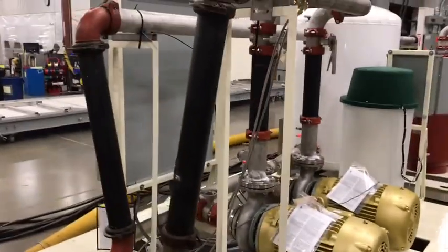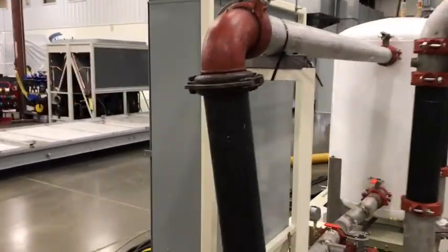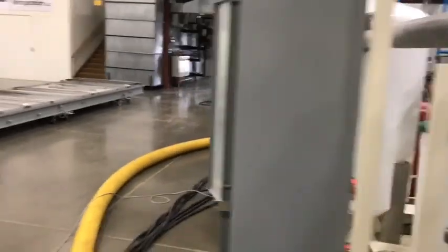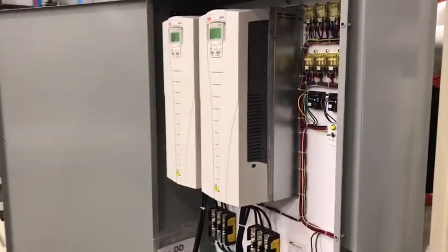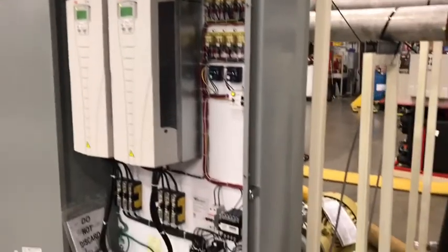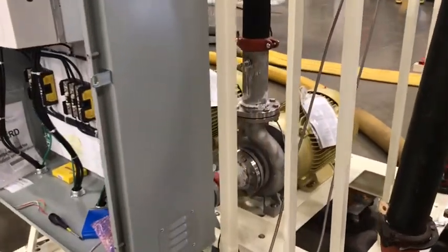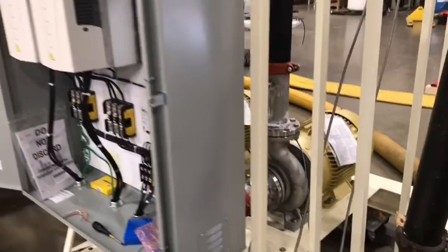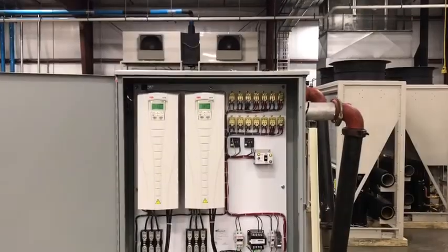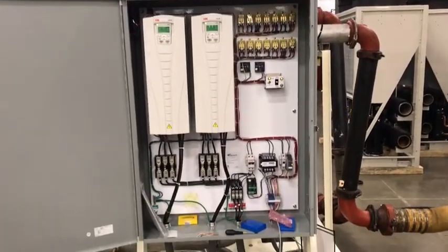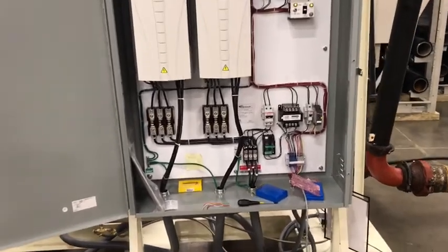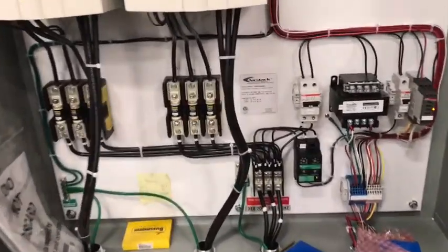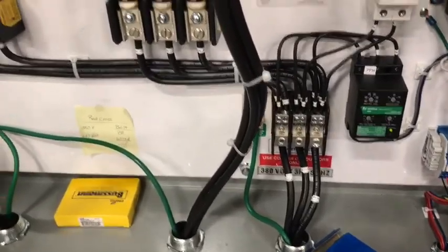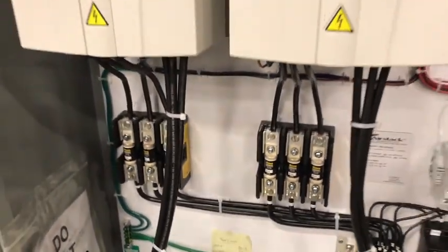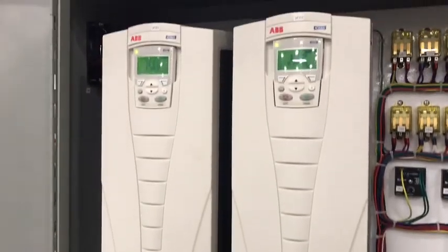We're going to work ourselves around to the control cabinet that's serving those primary pumps, the two larger pumps in the system. And we'll take a view of the components one by one. So starting here in the upper left, we have the VFDs, one for each of the pumps, ABB, ACH 550 type VFDs. We have power coming in down there at the bottom, coming up through fuses and then fed into the VFDs. I'll give you a close-up of the control panel here.